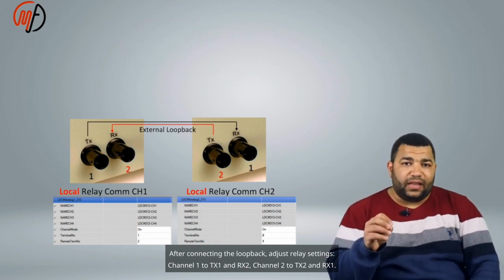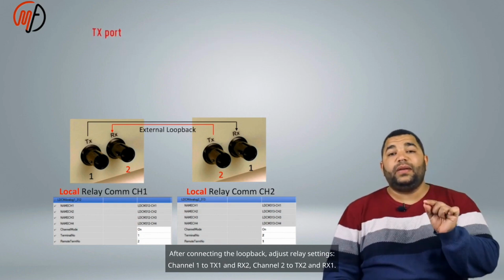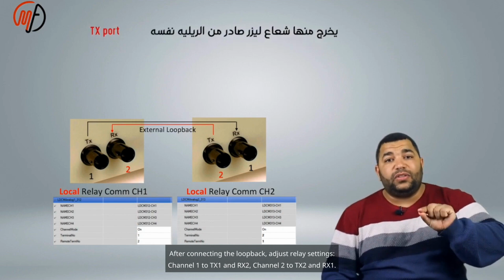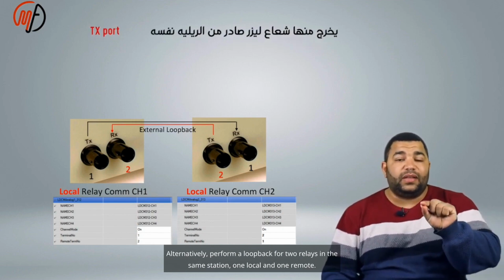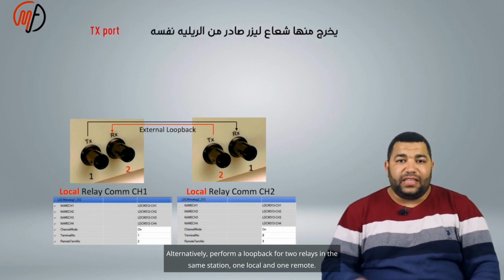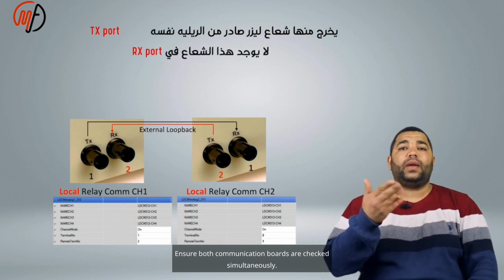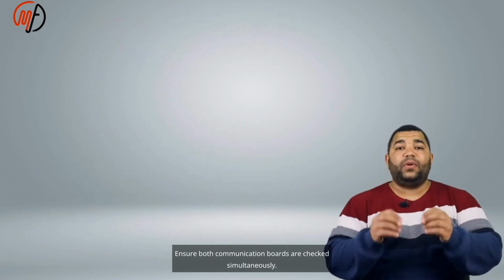After connecting the loopback, adjust relay settings. Channel 1 to TX1 and RX2, channel 2 to TX2 and RX1. Alternatively, perform a loopback for 2 relays in the same station, 1 local and 1 remote. Ensure both communication boards are checked simultaneously. Activate relay communication settings to on, set to 1 and 2 as master, and for the second relay, set to 2 and 1 as slave.